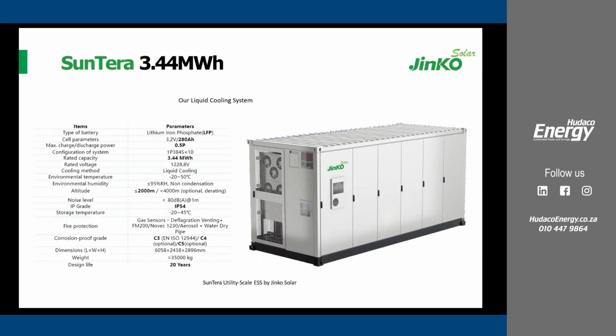Number two is that we also need to do proper electrical design, especially with cable sizing. It's very important, because I did some personal research on the cost of previous fire incidents that occurred, maybe not in Africa but in other regions. It was mostly either because of thermal runaway or cable undersizing, which leads to overheating of the cables and fire spreading into the system.